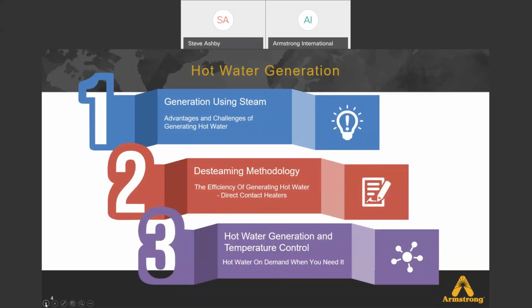So I want to break this down in 3 parts. One, generation using steam: talk about the advantages and the challenges of generating hot water with steam. We want to introduce the desteaming methodology, the efficiency of generating hot water, and we'll talk a little bit about alternate options to steam boilers. And then we want to review hot water generation and temperature control for the process side, where the demand is for hot water quickly and accurately.